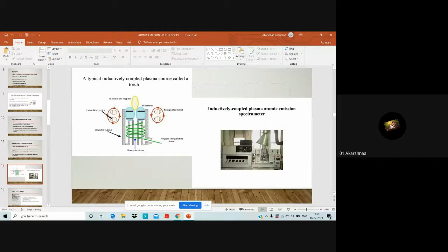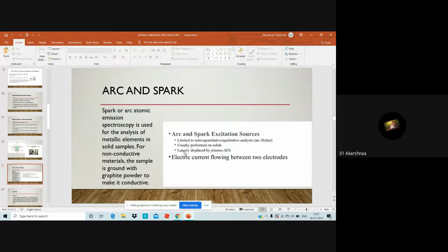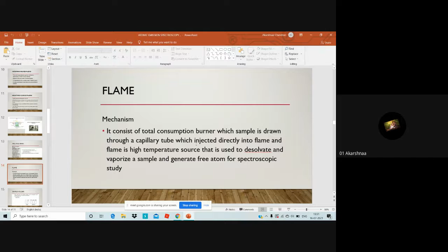And about arc and spark. Spark or arc atomic emission spectroscopy is used for the analysis of metallic elements in solid samples. For non-conductive materials, the sample is ground with graphite powder to make it conductive. It is usually performed on solids, largely displaced by plasma AES, with electric current flowing between two electrodes. About flame, it consists of a total consumption burner, in which the sample is drawn through a capillary tube and injected directly into the flame. The flame is a high temperature source that is used to desolvate and vaporize the sample and generate free atoms for spectroscopic study.